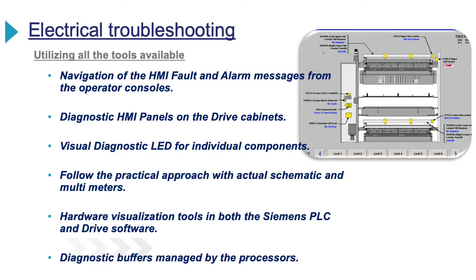On some presses, there are diagnostic panels available on the drive cabinets graphically displaying live I/O. Diagnostic LEDs on the hardware can display power, internal faults, and errors to the system. We'll move to the more intricate tools as the diagnostic buffers and the hardware configuration tools displaying the networks in the Siemens PLC with the S7 software. Starter software will also be used to view drive topology, networking, status and trace functions to check the actual drive and motor performance.